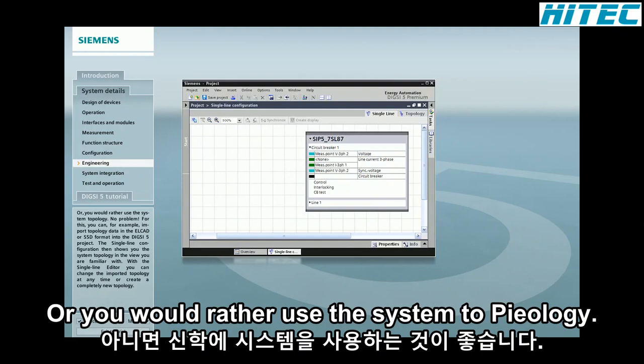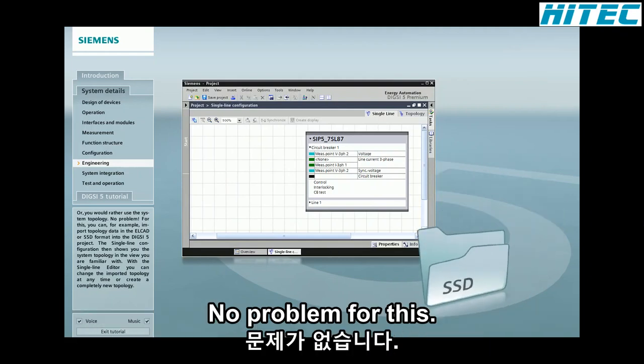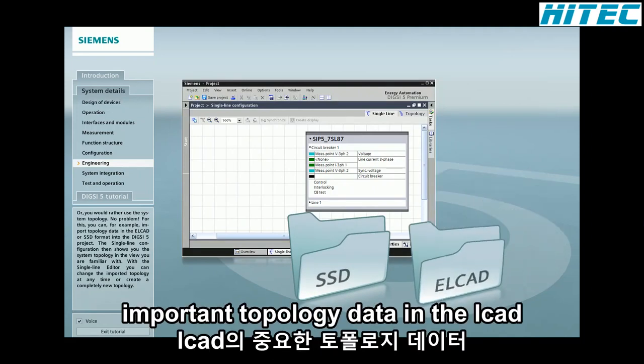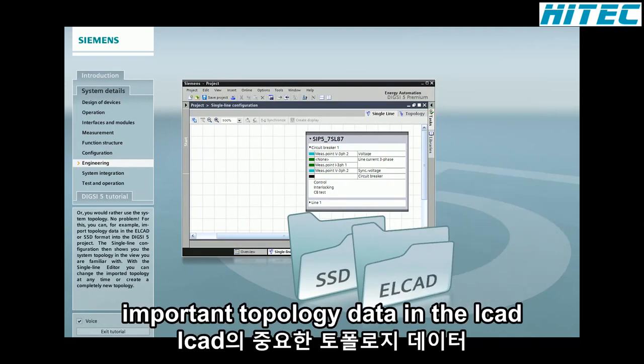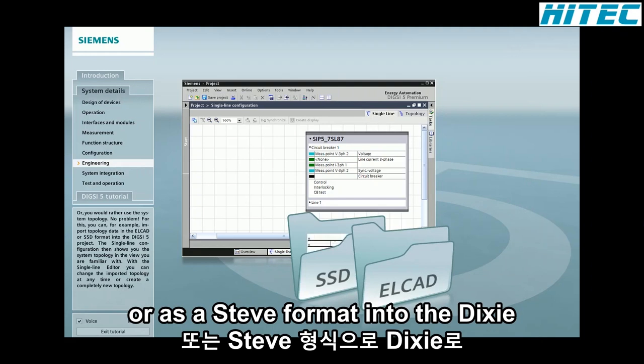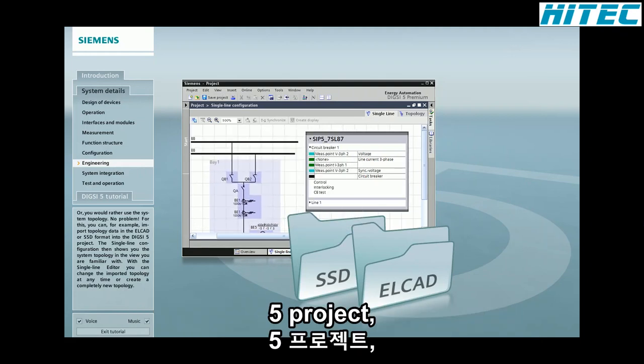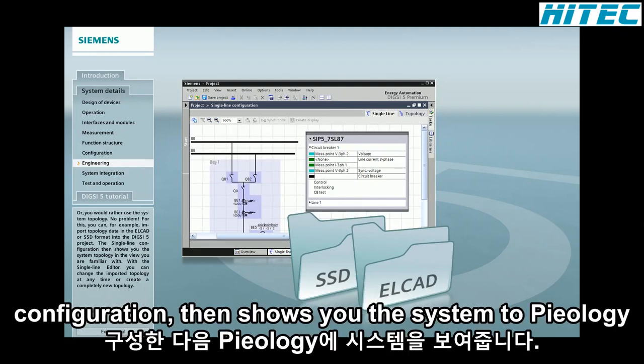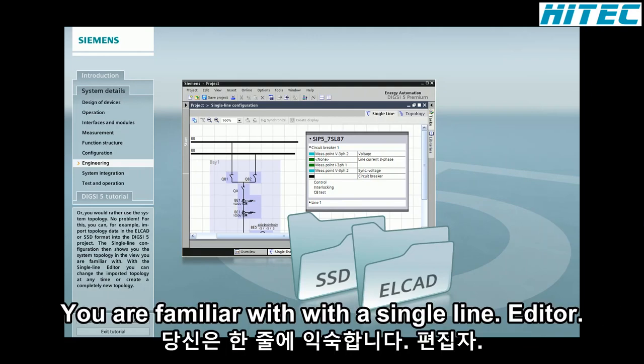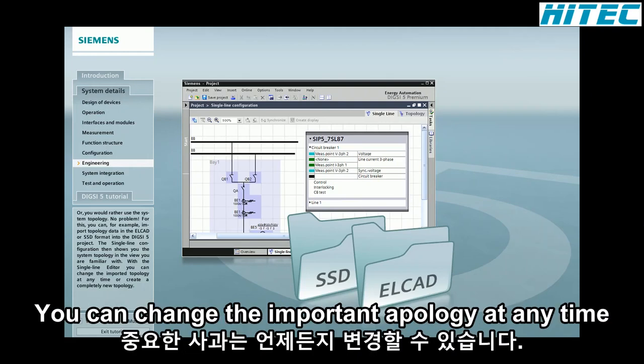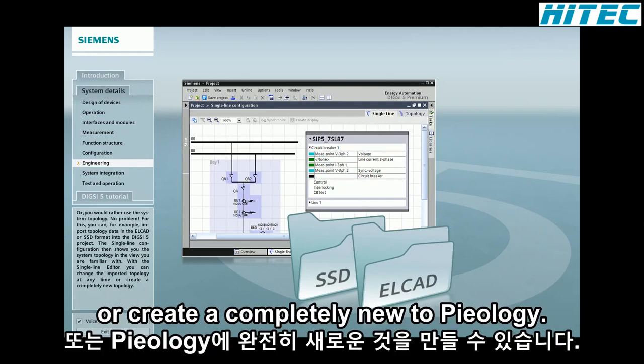Or you would rather use the system topology. No problem. For this, you can, for example, import topology data in the ELCAD or SSD format into the DIGSI-5 project. The single-line configuration then shows you the system topology in the view you are familiar with. With a single-line editor, you can change the imported topology at any time, or create a completely new topology.